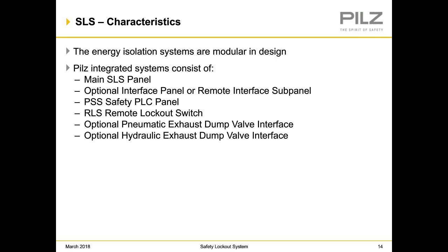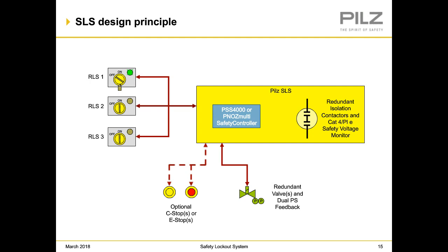And here is a schematic of a system, and we'll go through a lot more pictures, which will explain it in a little more detail. But you can see on the left-hand side, you have three remote lockout switches. Internally, in the safe lockout system, you have a safety controller, you have redundant contactors, and a safe voltage monitor. And also you have optional e-stops coming into the system, other safety stops, as well as redundant valves, maybe from a dual feedback system for pressure switches.